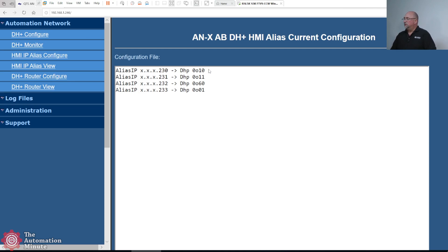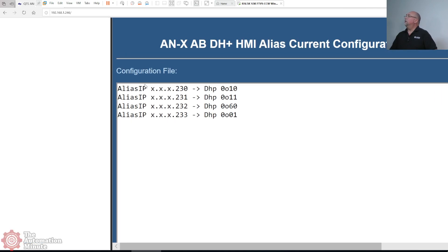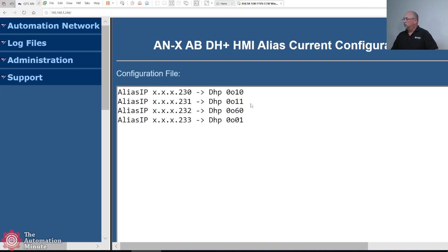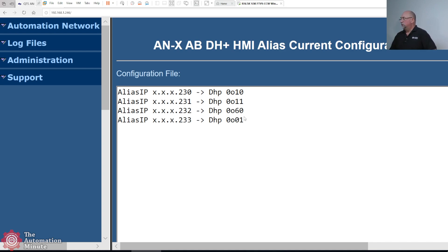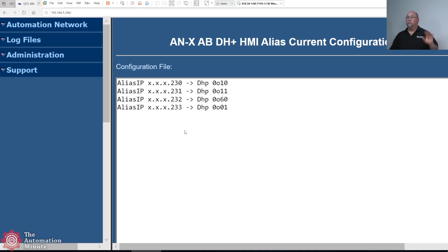You can see the alias IP, and this text comes right out of the manual. I've mapped my Data Highway Plus node 10 to 230.230, node 11 to 231, node 60 to 232, and my SLC504 at address 1 to 233. That's the first thing you do, and it will require you to reboot your ANX4.